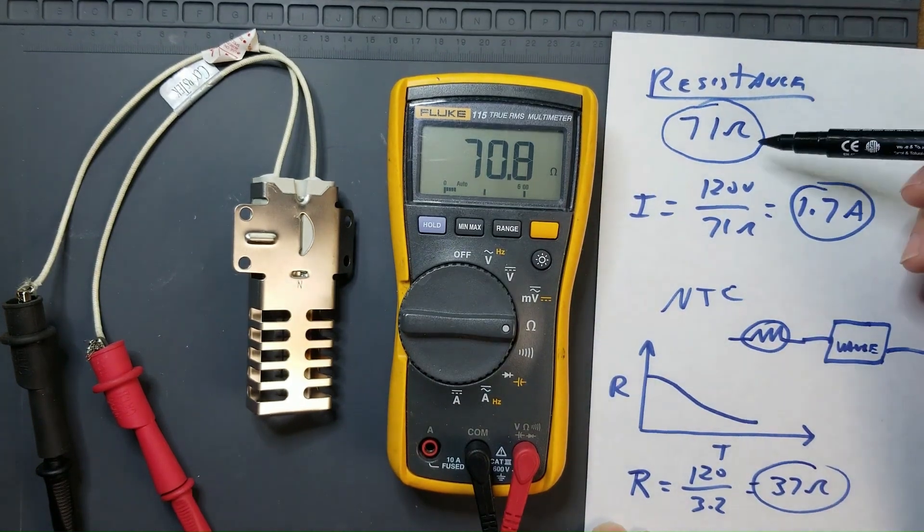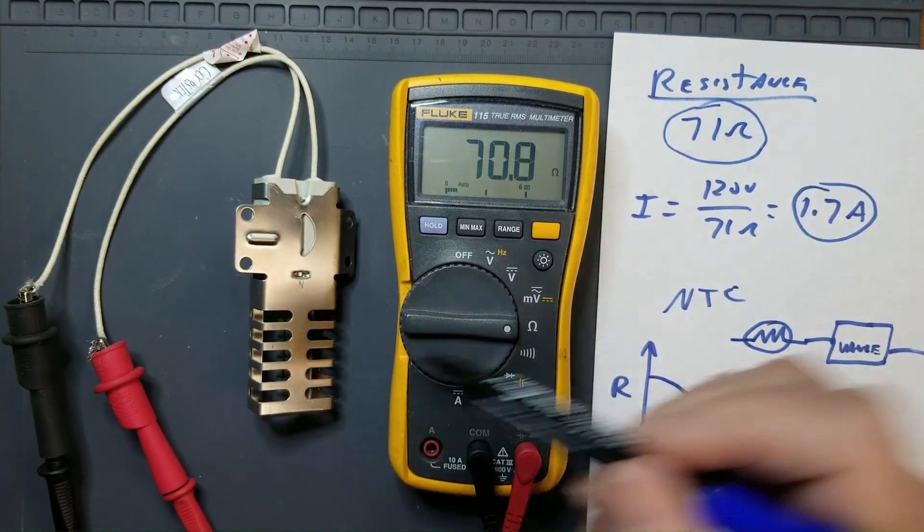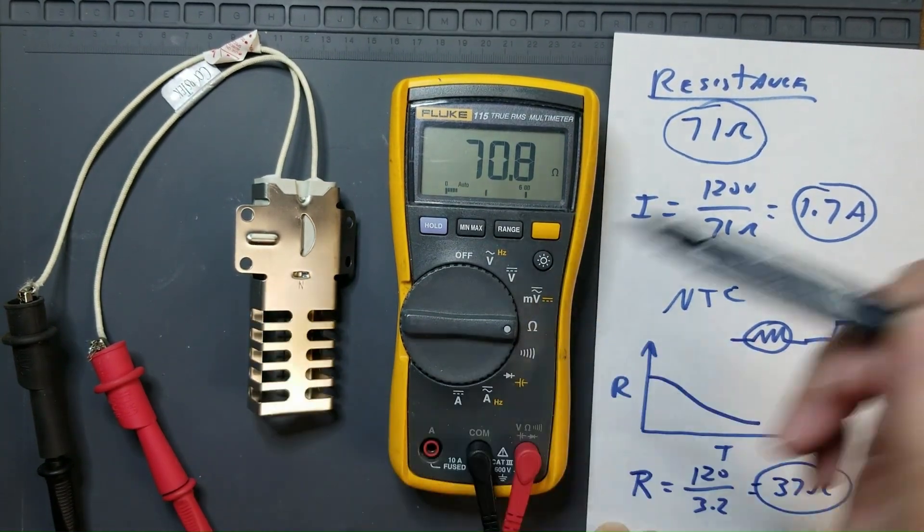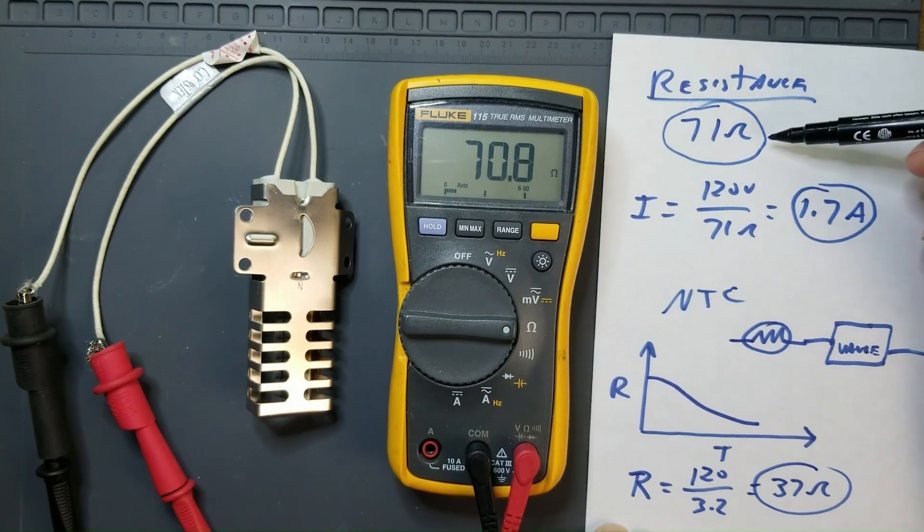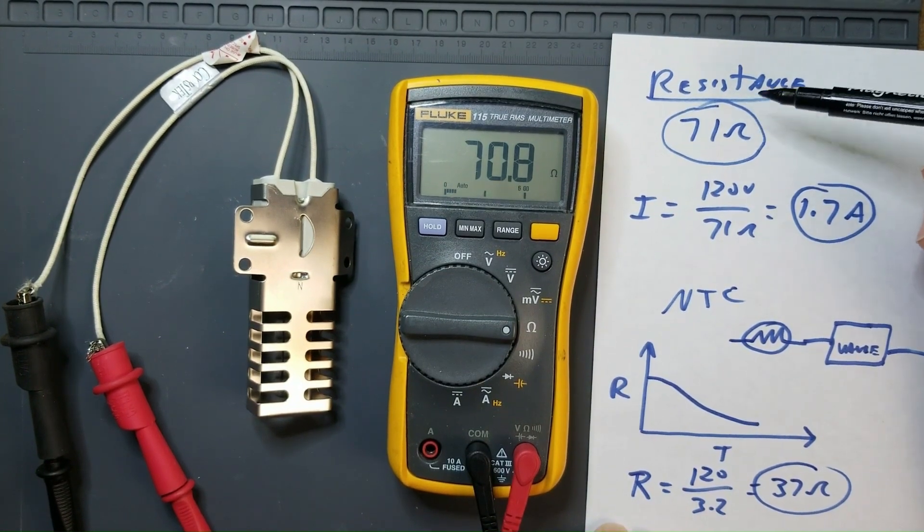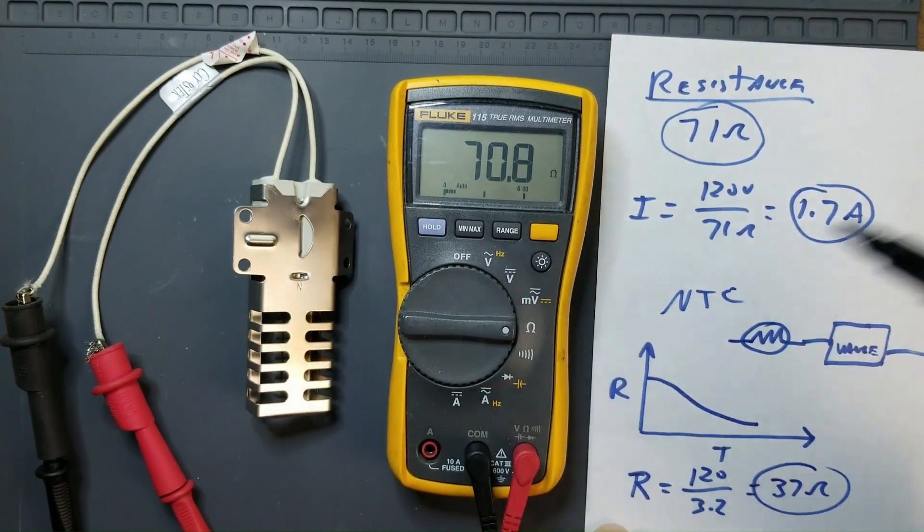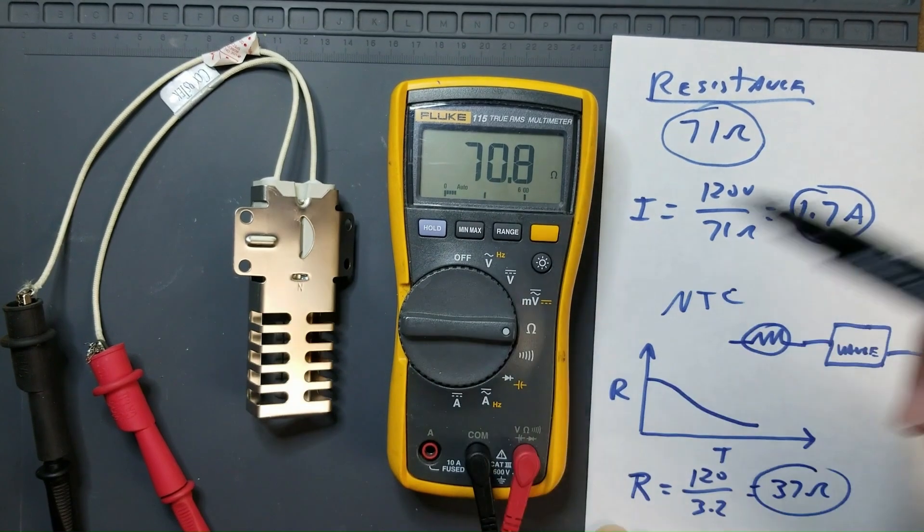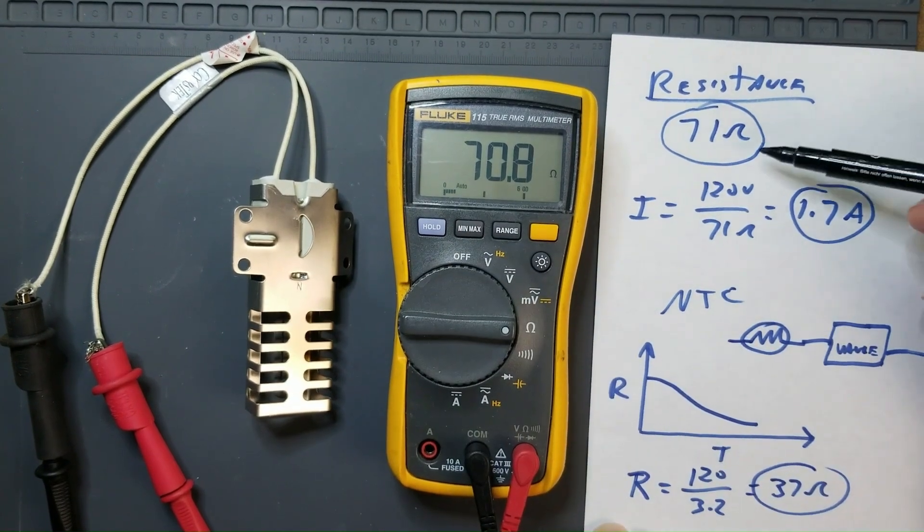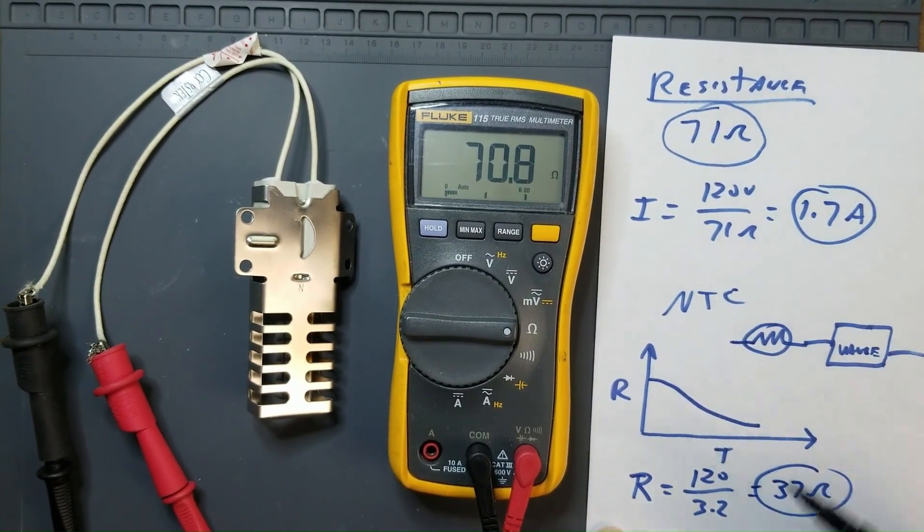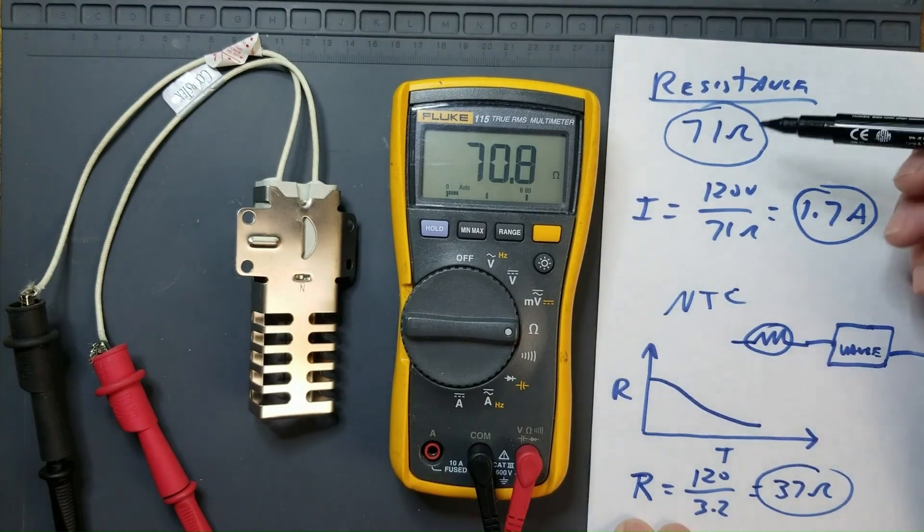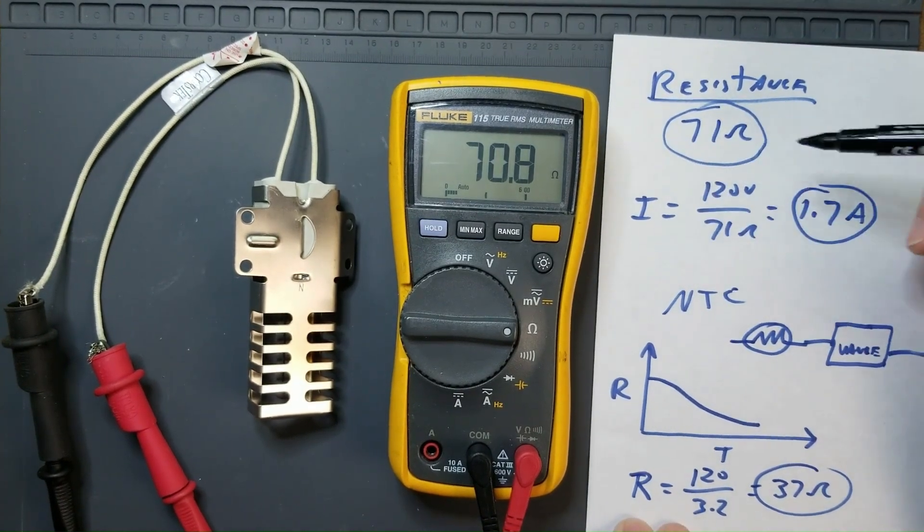So that's roughly half of what we measured here. So what that tells you is that this resistance measure, the measurement we took, the static resistance measurement, doesn't really tell you anything about the igniter other than that it's not open, broken and open, because that resistance is going to change drastically when it's in operation. So that's another way in which ohms can lie too.